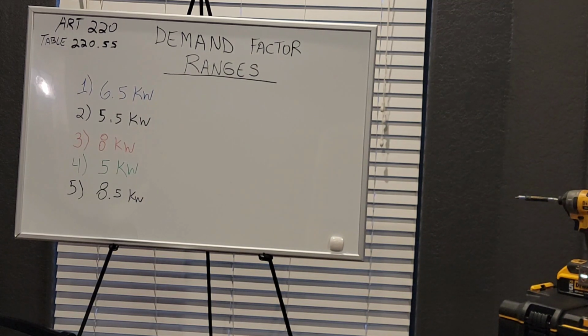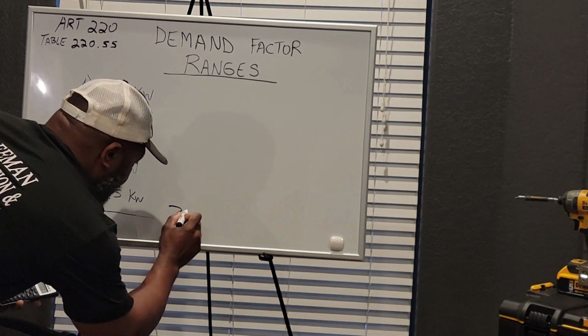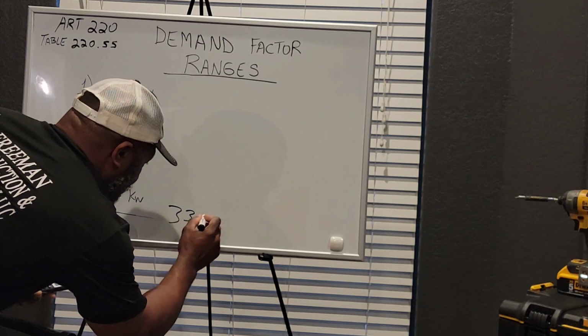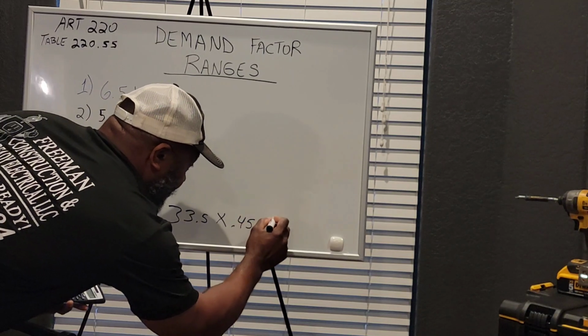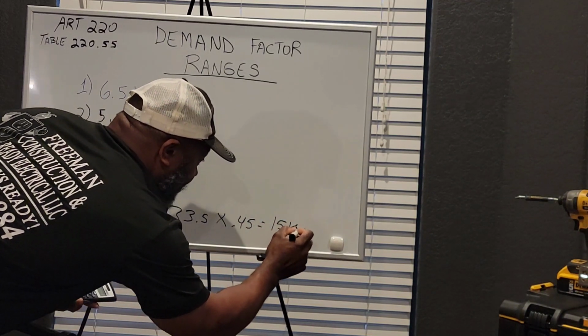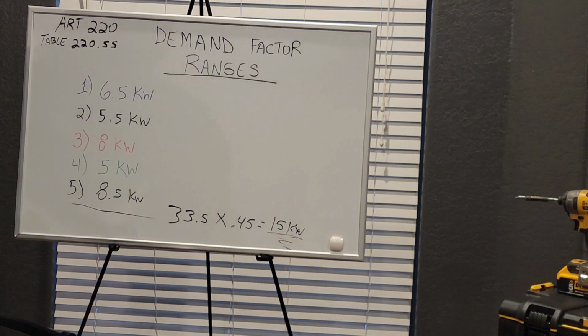I want to go ahead and put this on the board. 33.5 times your 45%. 15 kW. So that would be your maximum demand right there for those 5.